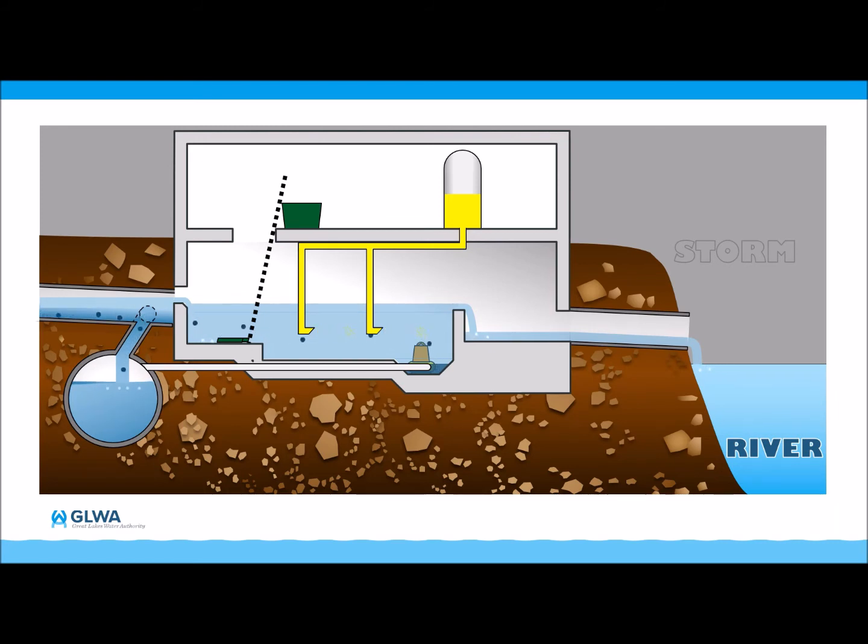In accordance with our National Pollutant Discharge Elimination System or NPDES permit, which is issued by the State of Michigan, we measure the volume of discharge for reporting purposes. This is accomplished by knowing the velocity of the flow and the level of the combined sewer overflow in the channel.